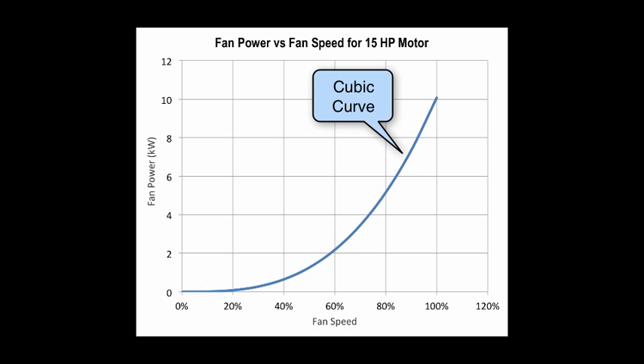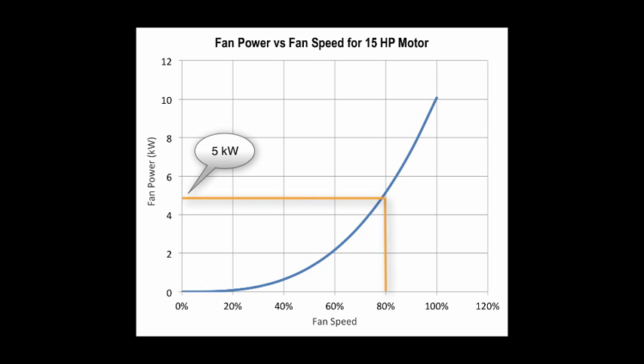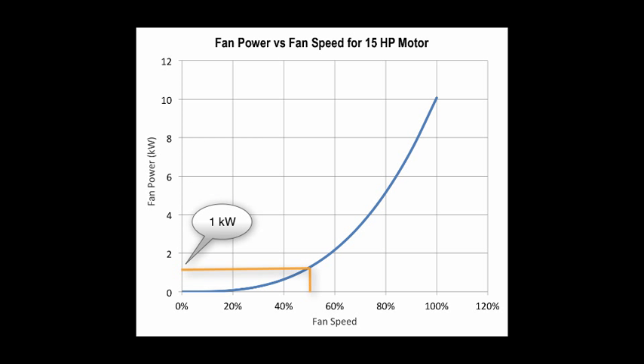So by reducing the fan speed from 100% to 80%, we're actually reducing the power from 10 kW to 5 kW. And if we reduce the fan speed even more, down to 50% speed, the power would reduce to about 1 kW. This relationship holds true no matter what motor size you have retrofitted.